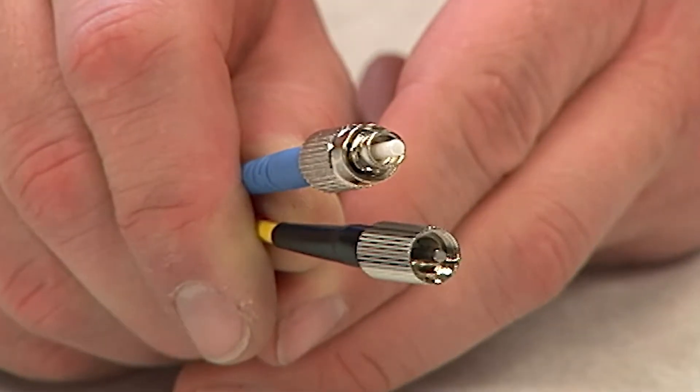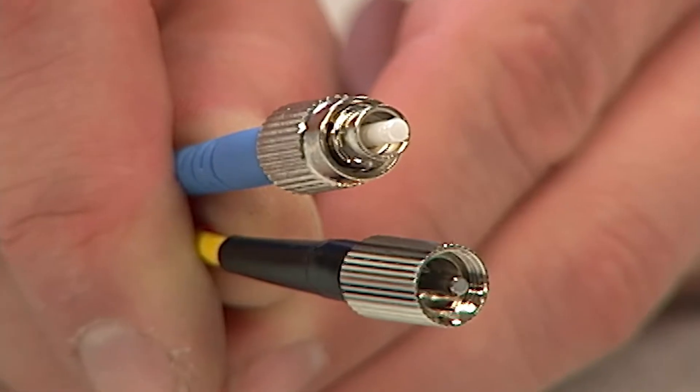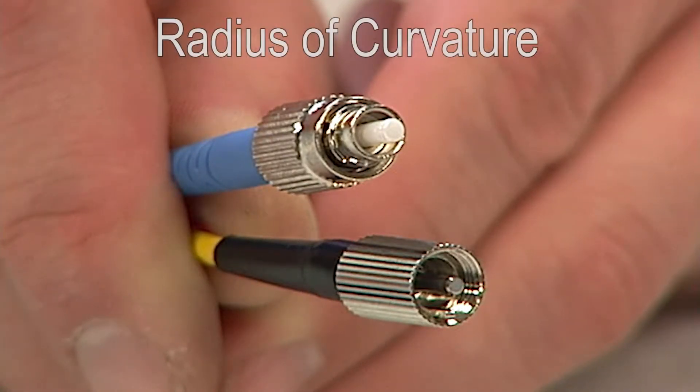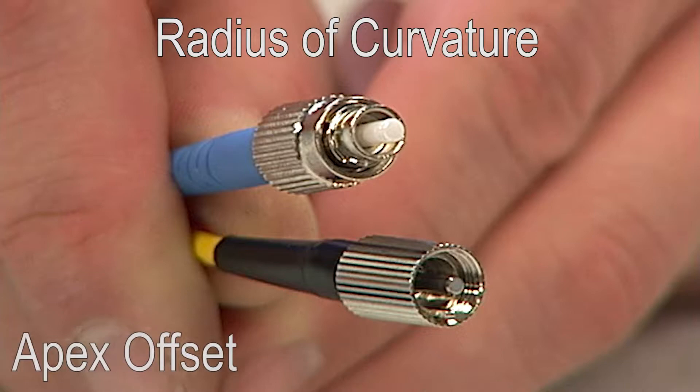Industry standards describe how to measure the three-dimensional properties of a ferrule end-face. The three main properties measured are radius of curvature, apex offset, and fiber height relative to the ferrule surface.